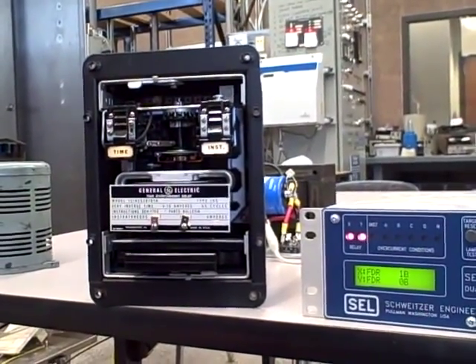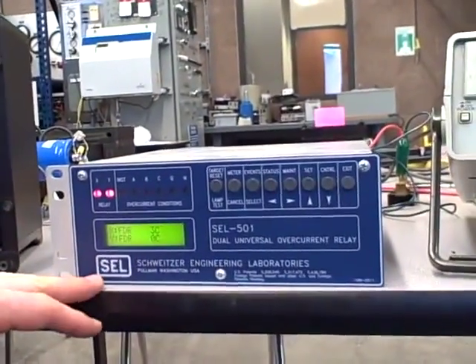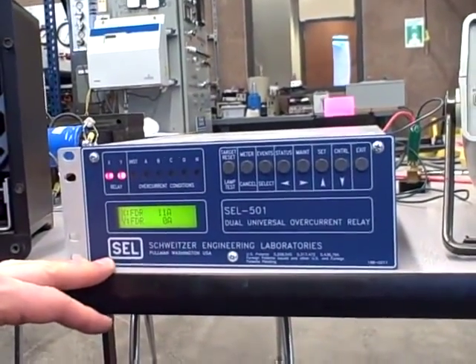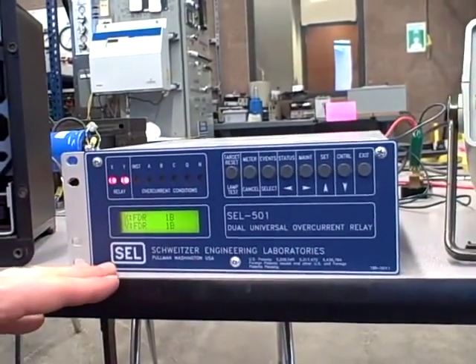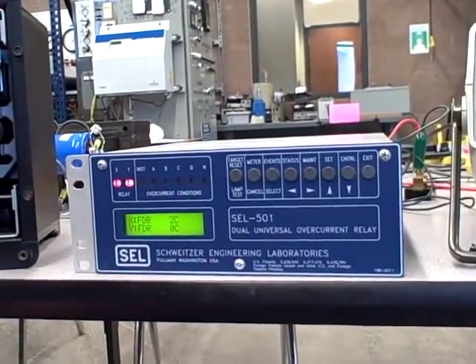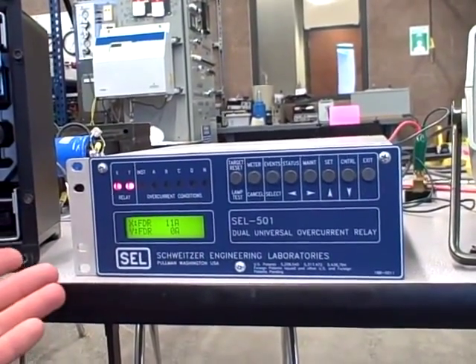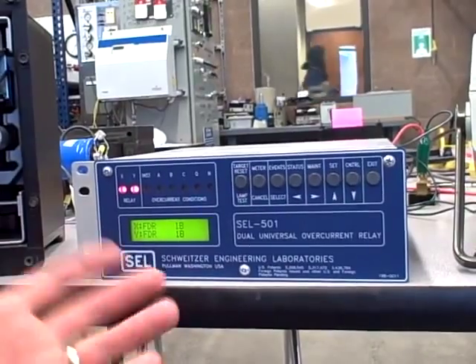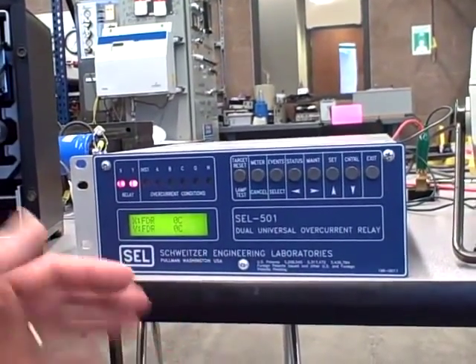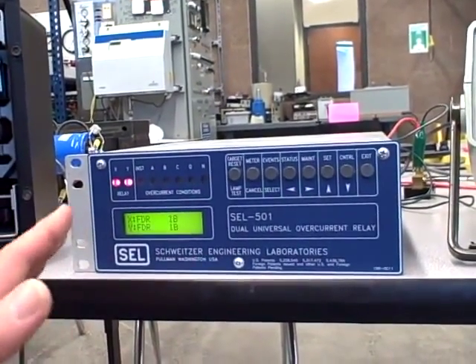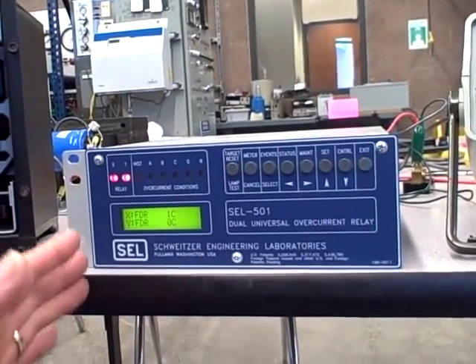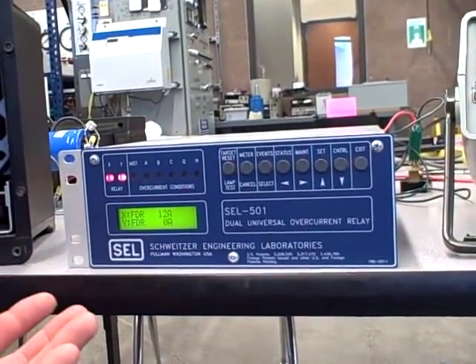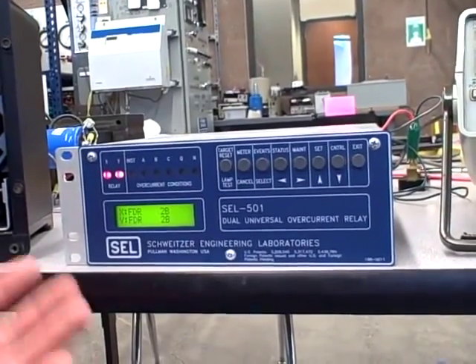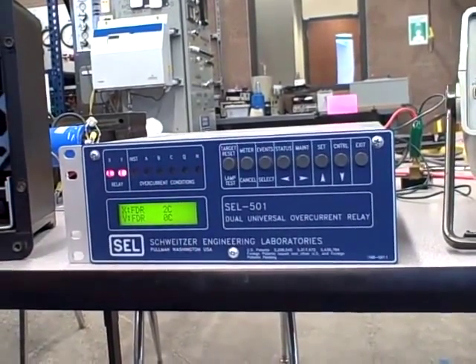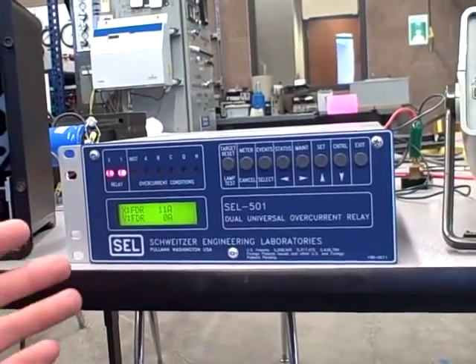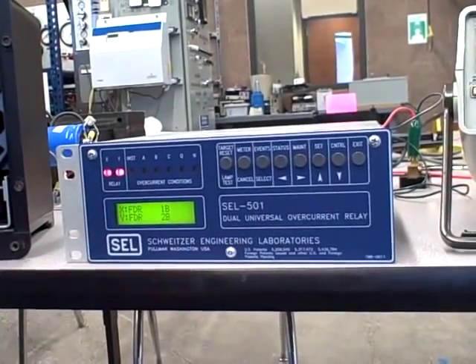What we're doing now is we're going to take a look at the more modern version, this one made by Schweitzer Engineering. There are other companies too, including General Electric under the Multilin brand that makes modern protective relays. This is microprocessor based, so there are no moving parts in this relay. There's no disk, there's no time dial, there's no mechanical targets, but we use a lot of the same terminology. So when you look through the manual on this and you look at the settings, you'll see things like time dial setting or target that harken back to the days of electromechanical relays, but same functions, different implementation.